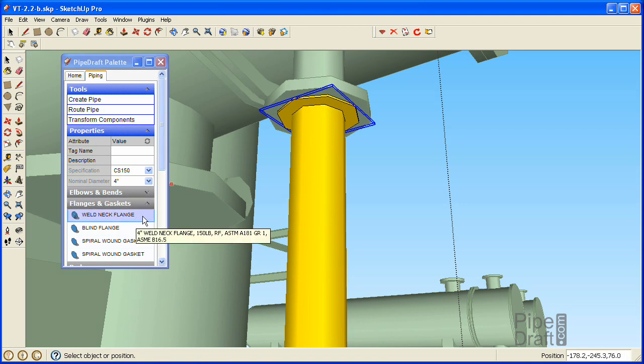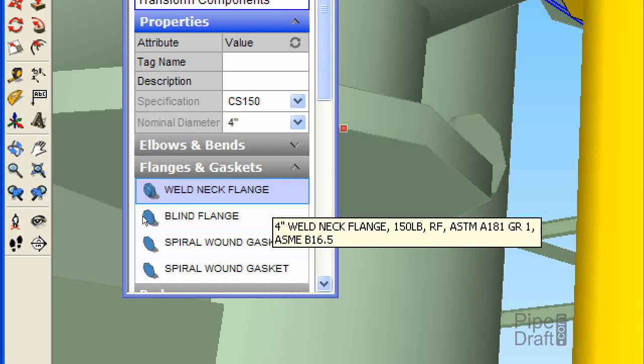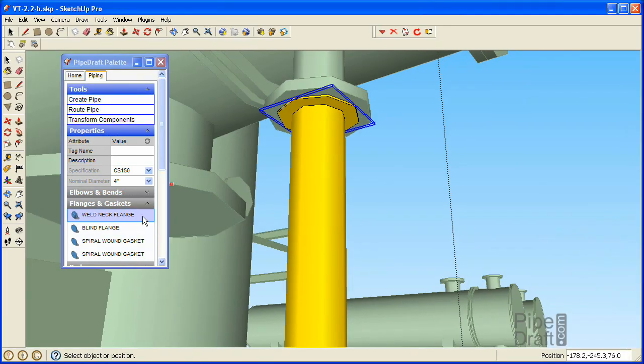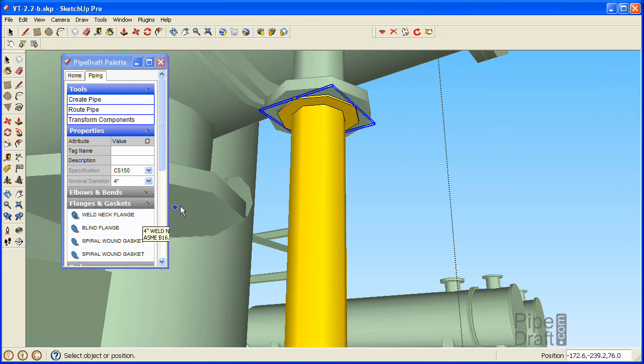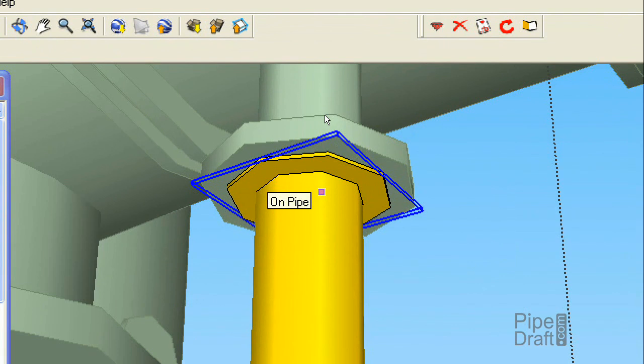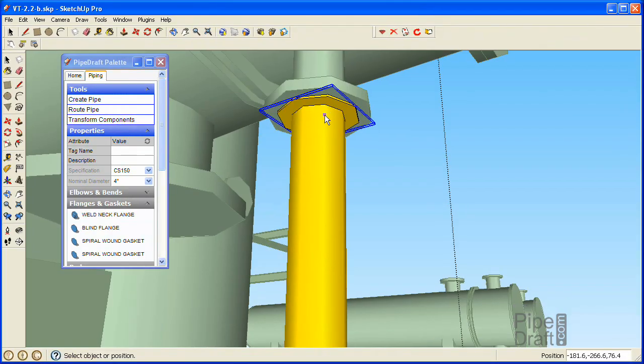Click the weld neck flange choice in the palette, then click a position on the vertical pipe that is close to the end of the pipe segment near the gasket. We want PipeDraft to nibble away the pipe segment to make room for the flange, which will also position it at the face of the gasket.